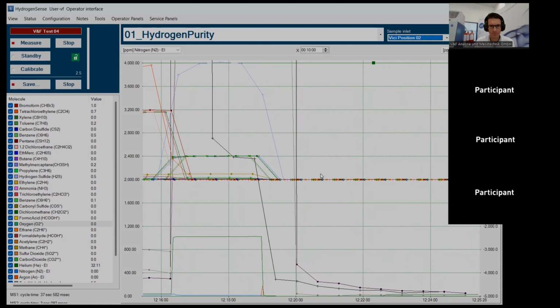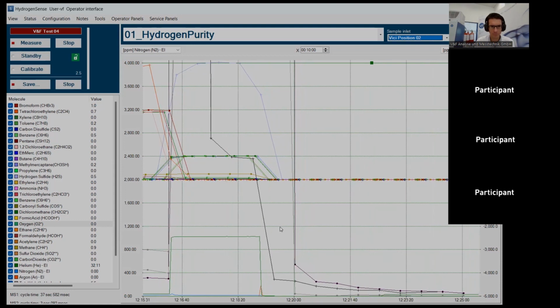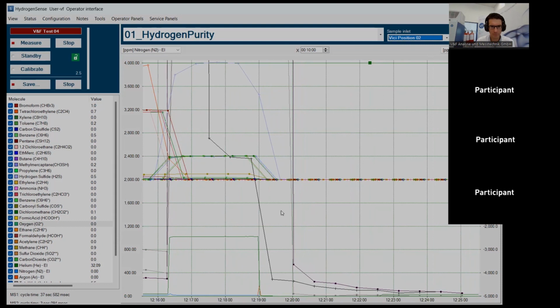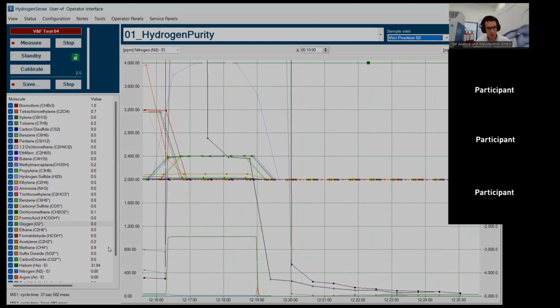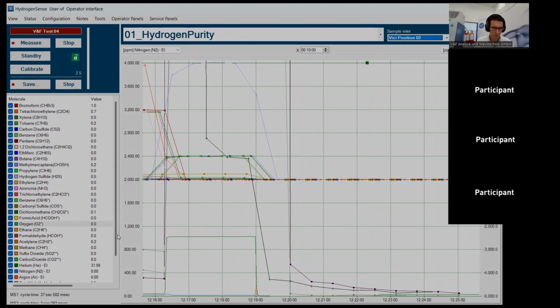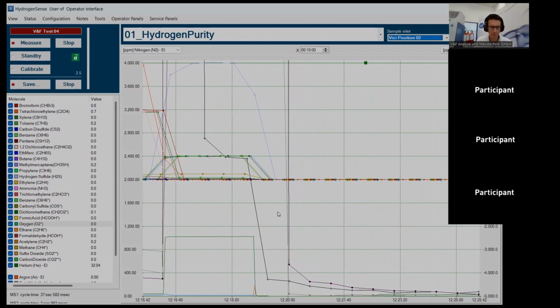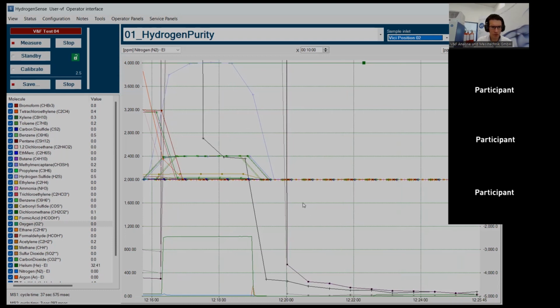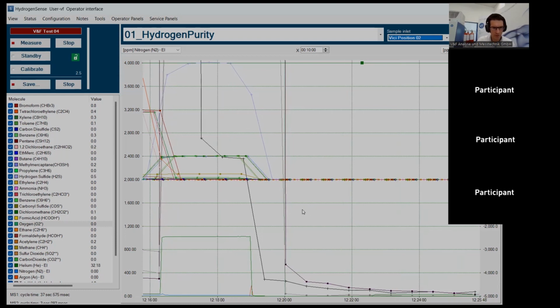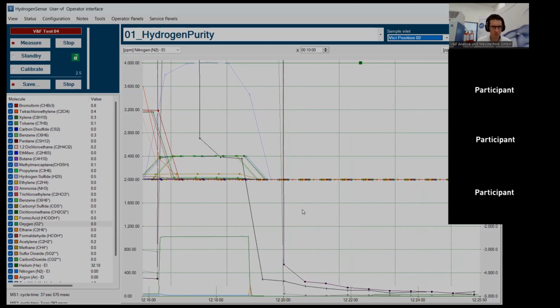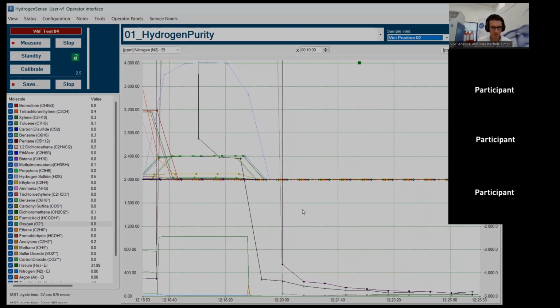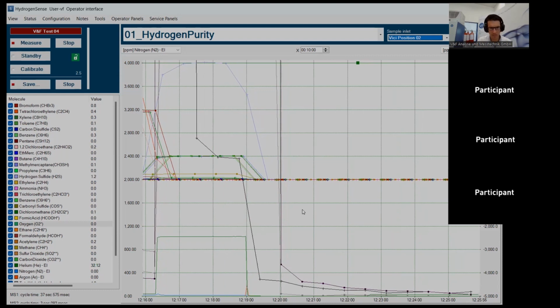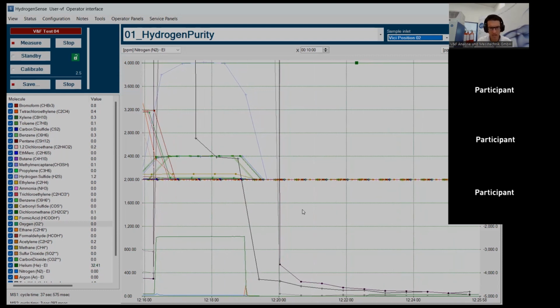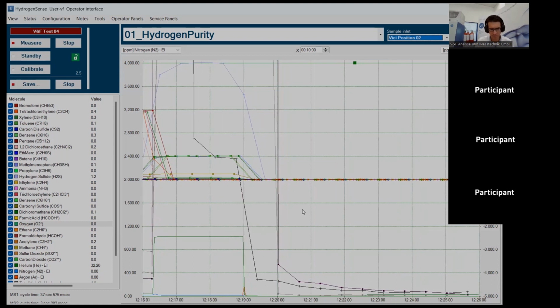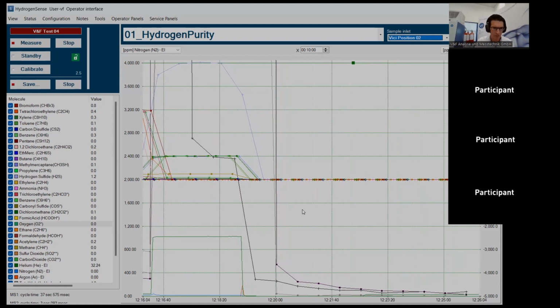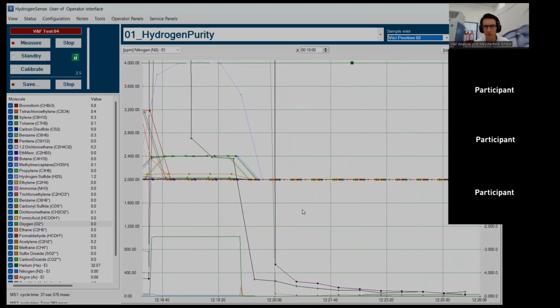Can you repeat on carbon monoxide, what is the least detection limit for carbon monoxide? For carbon monoxide on this Siemens analyzer that we are using for it, it's 100 ppb. So at this stage, the limit in the regulation is 200 ppb. So it pretty much gives you a good or bad criteria. The quantification will not be as precise as saying it is 15 or 20 ppb. You can pretty much say, all right, it's below 200 or it's above 200.